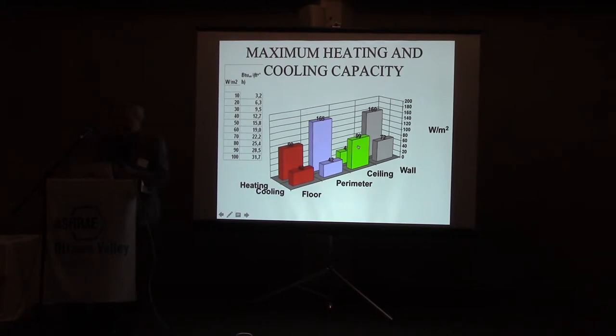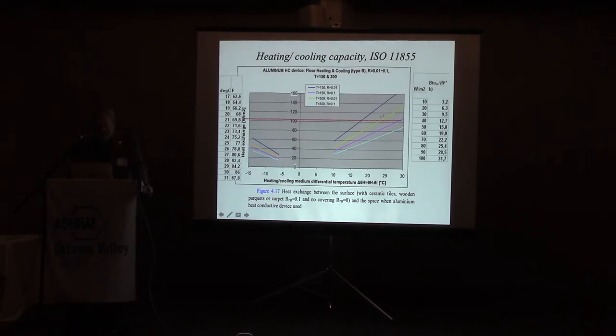If you want to see how much heat output or how much heat you can remove, the manufacturers may have diagrams or calculations. You can go in depending on pipe distance and delta T between your water and the room, and find what is the heat exchange. I'm not going into detail with that.